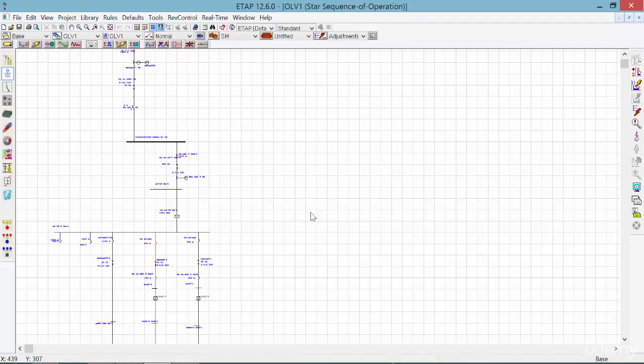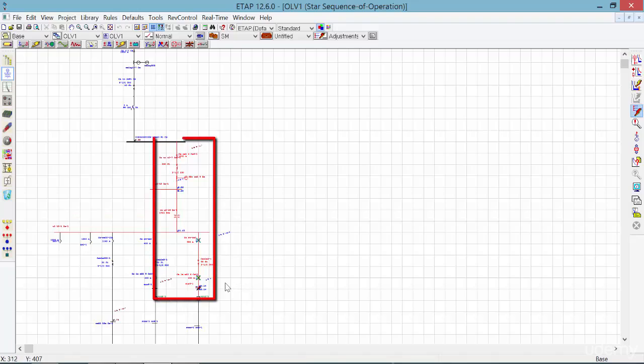Now let's together create a time current curve, and using this curve, let's talk about how by putting a fault somewhere downstream in our system, we're going to get a correct sequence of operation for each of the circuit breakers in that branch. So what I'm going to do, I'm going to select the right branch from the high voltage circuit breaker all the way down to the bus upstream of the VFD. But before creating the time current curve, I'm going to put a fault and run the simulation again. And while it is being run, I'm going to select the right branch again from the high voltage breaker all the way down to the bus upstream of the VFD.